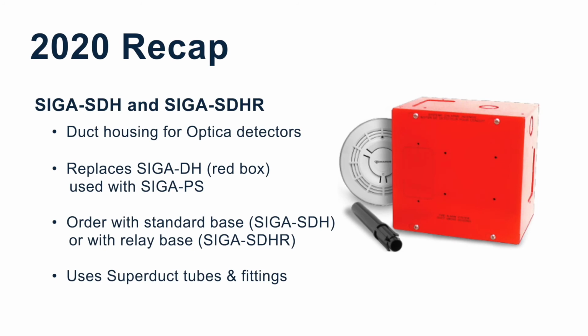This replaces the SIGA DH, which used the SIGA PS, which is no longer manufactured. This new housing works with Optica by encasing the entire detector. To install or remove the detector, remove the front cover, remove the back housing, and put in the detector. A base comes pre-wired in the housing, which drives two models. One is the SDH, which has a pre-wired standard base, and the SDHR, which has a pre-wired relay base. This unit also uses the SD inlet tubes with the snap fitting on the pipe end.